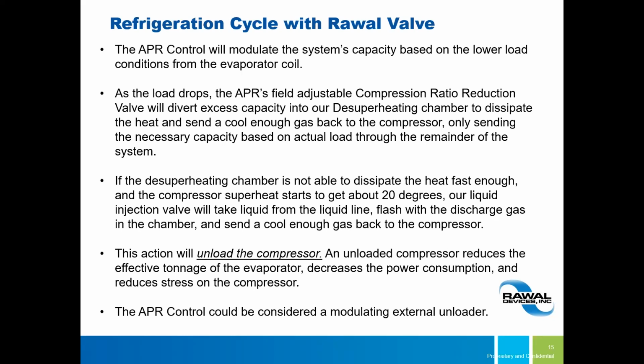If your desuperheating chamber isn't big enough to get rid of that heat, and your compressor superheat gets up some, then your liquid line will start injecting into the system, and you'll send cooler gas back into the compressor. Essentially, you're causing an unload of the compressor, and when you unload the compressor, you're reducing the tonnage of the evaporator, and that lowers your power consumption and helps your compressor out some. So think of it as an external device that allows you to modulate your compressor. And I hope I haven't hacked this up.